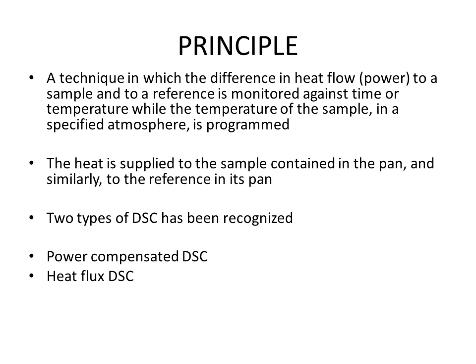The principle of DSC: it is a technique in which the difference in heat flow — that is, power to the sample or to a reference — is monitored against time or temperature while the temperature of the sample in a specified atmosphere is programmed. In this technique we measure how much power is given to the sample and reference, so their difference is calculated and we get the enthalpy of transition. On the x-axis there is temperature or time.